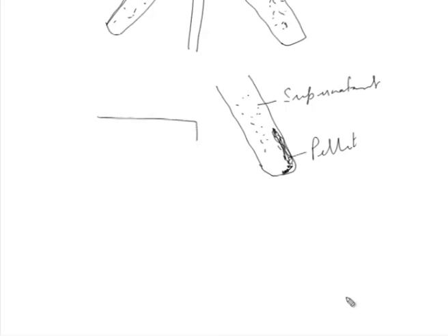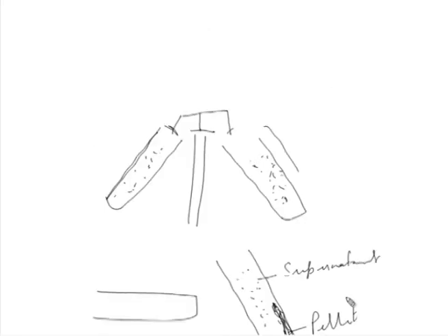If it is a swinging bucket rotor, when the centrifuge is switched on, the buckets will swing out, because they are free, they are not constrained like in here, where the tube is constrained in the slot, but these are open. So, they just fly open, and their pellet will be at the bottom, because the centrifugal force is in this direction. Here the centrifugal force is in this direction, therefore the pelleting will take place on this wall. Likewise in vertical tube rotors it will happen.